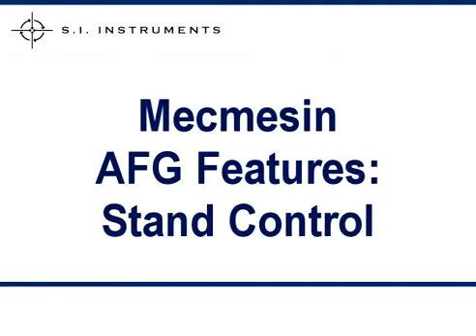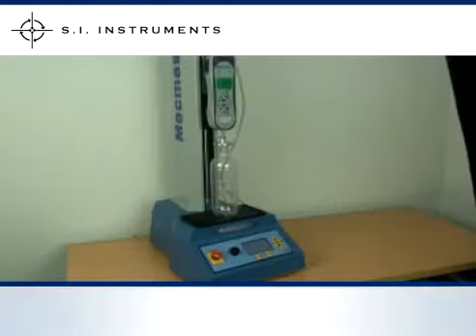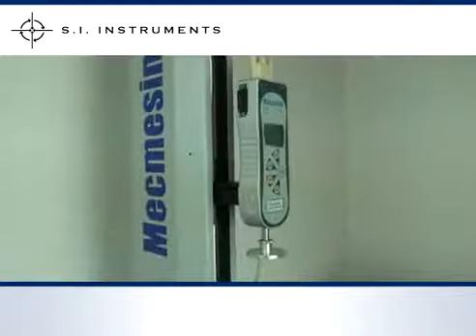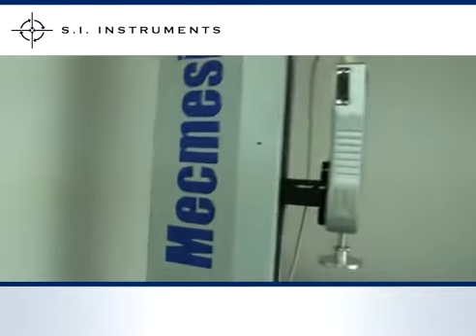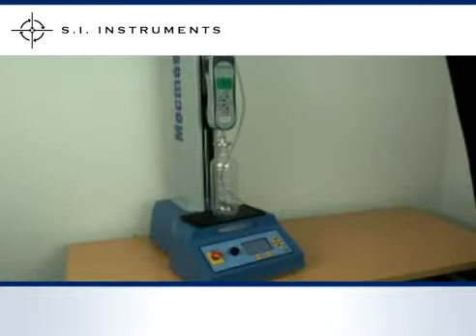When the Mecmesin Advanced Force Gauge is used in conjunction with a Mecmesin Multitest D test stand, the gauge can travel between the limit switches. However, it is also possible for the Advanced Force Gauge to signal the stand when the test has been completed. This feature is a perfect time-saving operation. The feedback can be either by detecting a break or collapse point or at a pre-programmed force.